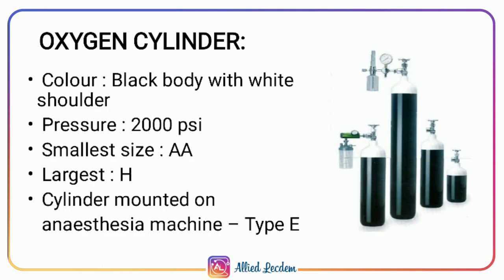The oxygen cylinder has a black body with a white shoulder. The pressure in the cylinder is 2000 psi (pounds per square inch). The smallest size is double-A and the largest is size H. The cylinder mounted on the anesthesia machine is type E. A fully loaded cylinder has a pressure of 2000 psi, and on usage the pressure gradually decreases.